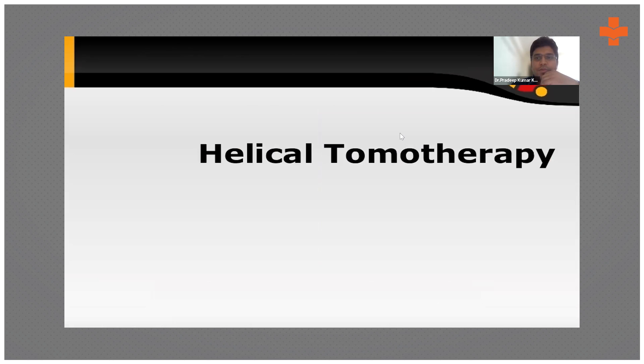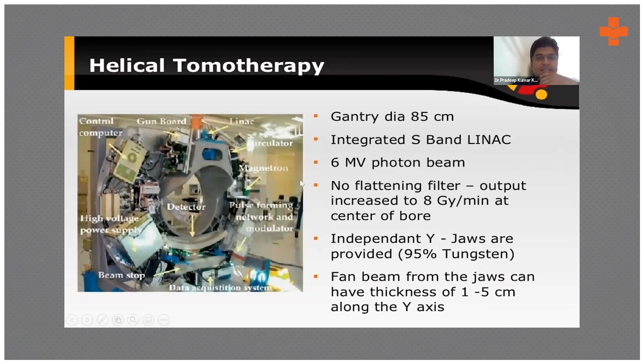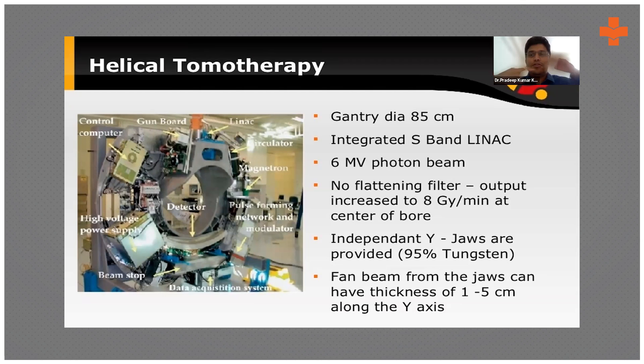One newer technique is helical tomotherapy. As previously mentioned, it is a linac mounted on a CT scanner. As the CT performs a helical motion, the linac also continuously moves in a helical motion and delivers radiation in a helical manner. The specialty of tomotherapy is its binary MLC — there are MLCs throughout 360 degrees that can open and close independently. In normal MLCs they must move continuously, but in binary MLCs there is no need for continuation; they can open or close anywhere.